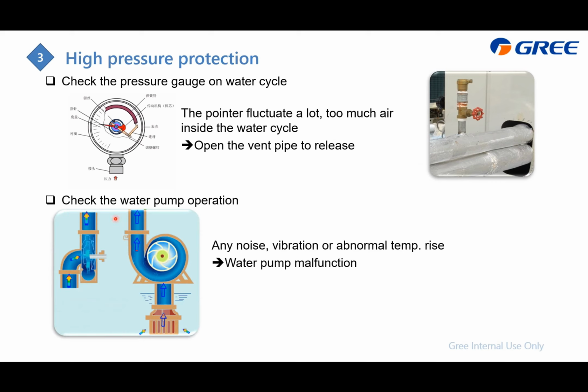And then to check the water pump, the purpose is to ensure it has enough water flow rate. To check the water pump, you can touch it to feel the vibration or listen for any noise. And also if the water pump has an abnormal temperature rise, that also means there is something wrong with it.